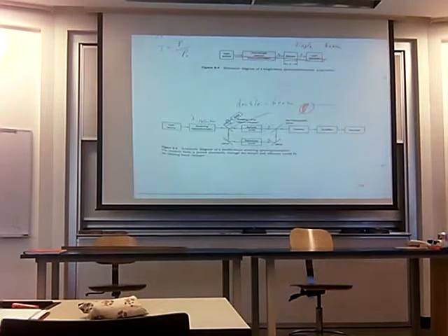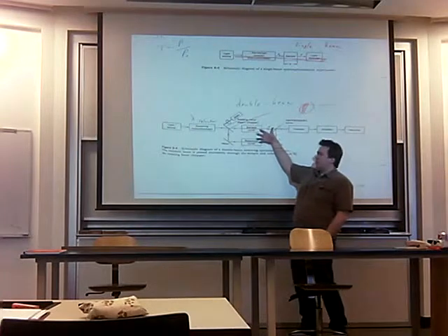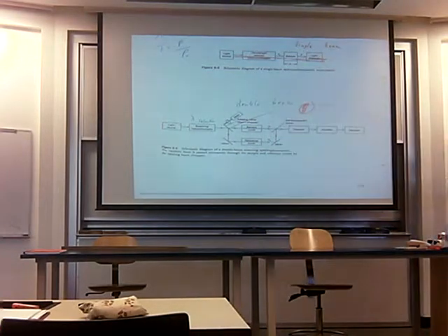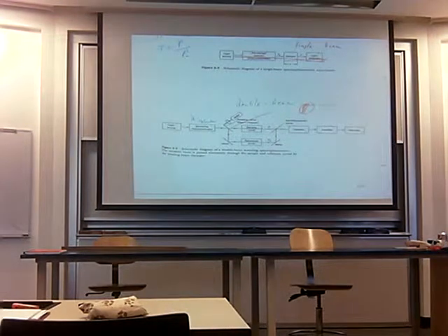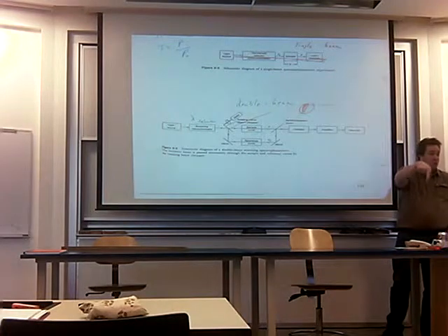You have probably all used a double beam instrument. I can't remember exactly what we got, but I think we got them all before we started in first year. The Shimadzus that I think are used in the first year lab, whether it's 121 or 125, they're double beam instruments. You open them up, there's actually two places to put a cuvette. Now you may have only used them as a single beam, you may have only used one cuvette.